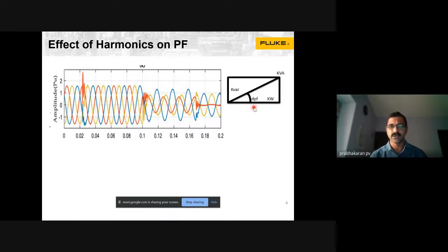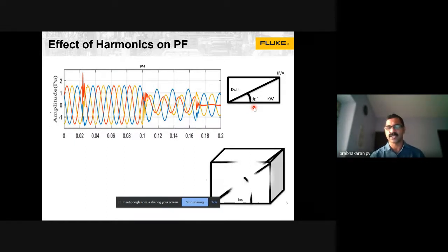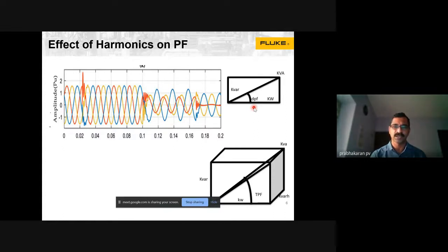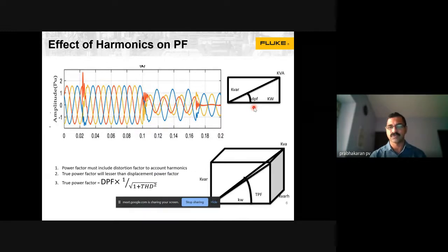When you introduce power quality issues or harmonics, an additional component called kVARh, the harmonic kVA, comes into the picture, pushing the power factor further and introducing the term true power factor. This true power factor is actually your real power factor, and it pushes the limits of your utility supply or capacity further, reducing your actual available power usage.